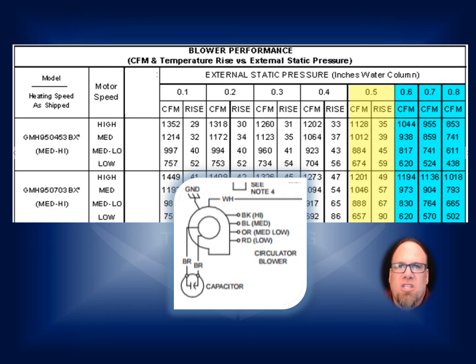So here's a more expanded blower performance chart as far as your static pressure chart. If you look over to the left, it shows you the model of the equipment, and you have to make sure that you're looking at the right model. For instance, the one that's up at the top there, the GMH950453BX. It's telling you that you've got your fan speeds set at medium and high. So your medium is going to be your furnace speed on high, and then your high speed is going to be your air conditioning speed.